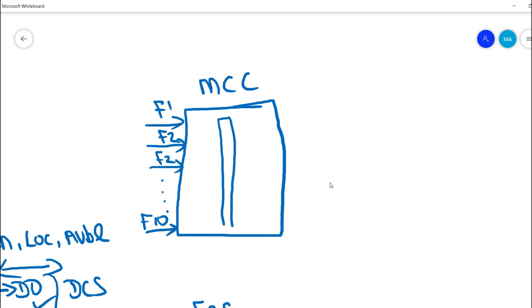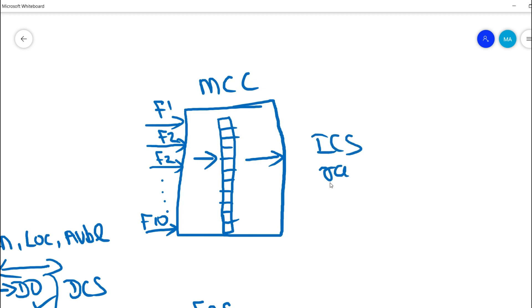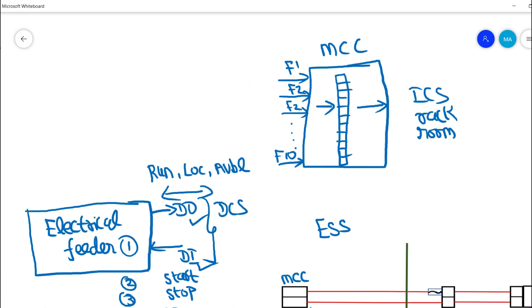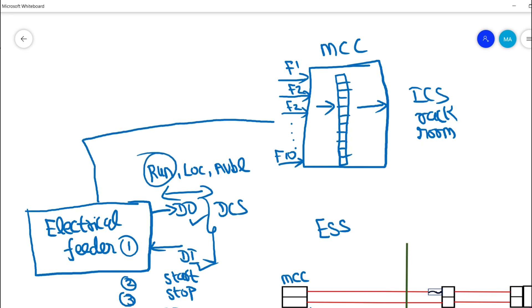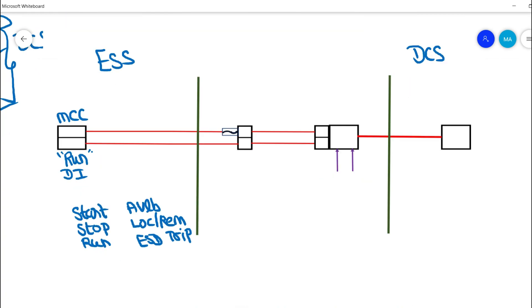We have an interfacing terminal block (TB) where all these control supply signals are terminated. From here, a multicore cable runs into the ICS rackroom. So the signal flow goes from electrical feeder to MCC, and from MCC the run feedback is taken into the ICS rackroom. This is the motor control circuit.